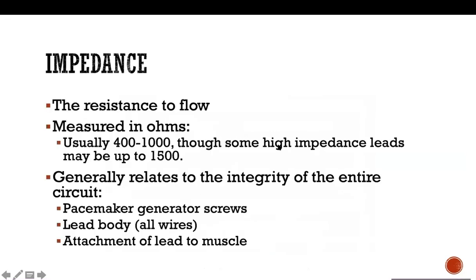Okay. The third thing we do with a pacemaker is the impedance, which is the resistance of the lead itself, because there is metal, there is silicon, and there is some energy going through it. So there is a little bit of resistance. For example, water has resistance, any metal thing has resistance, anything has a resistance. In a closed system, what I mean by closed system is the lead is connected to the device in one area and connected to the myocardium in one area, the resistance is usually ranging between 500 and some 1500. So that's usually the normal pacing impedance.